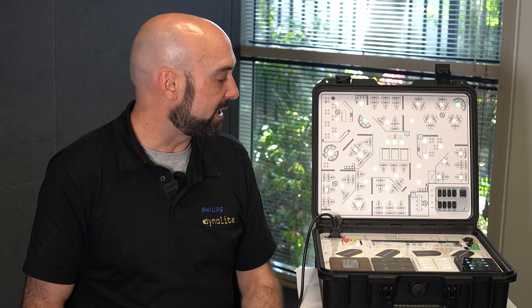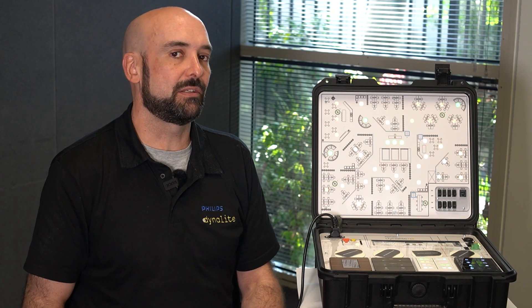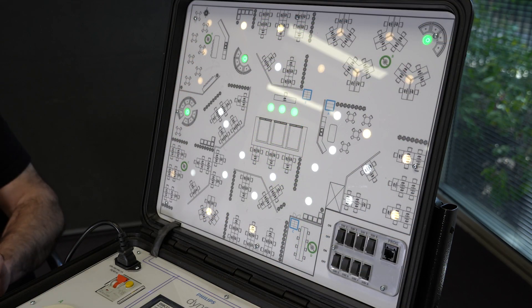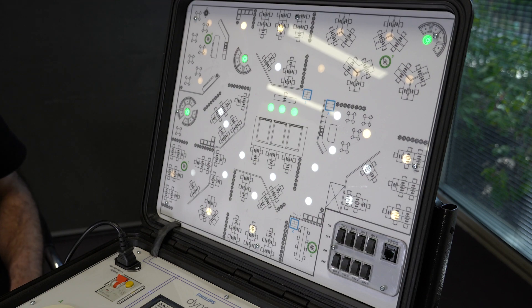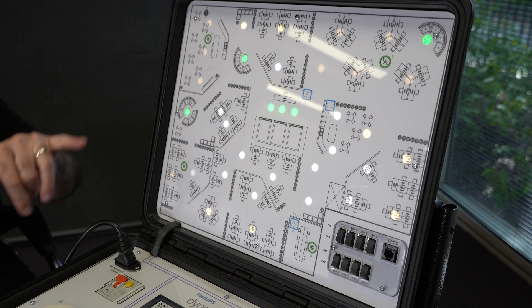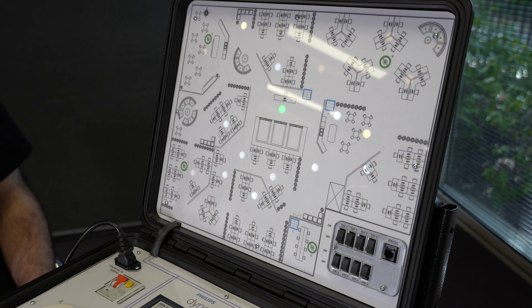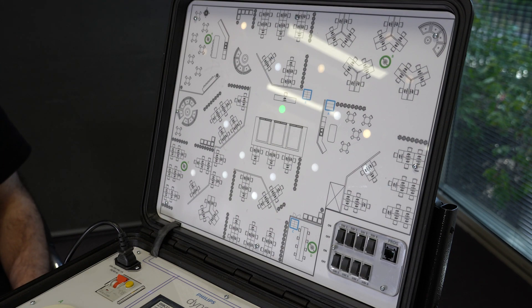Additional functionality is power demand response. When power companies need to reduce load on their supply, they send a message to the project asking it to shed HVAC and lighting loads. The system receives this message and begins to dim or switch off lighting to accommodate the load-shedding requirements. There are multiple stages: some lamps switch off, some dim, and in the most extreme cases lamps dim right down so only the absolutely essential lamps remain on while still maintaining occupancy comfort.